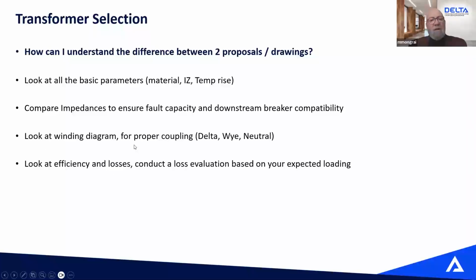Make sure the winding diagram has the proper coupling. Is it delta, is it Y, do I need a neutral? Again, look at your efficiency and losses, and you can conduct a loss evaluation. If you're buying a big lot of transformers or a large transformer, just don't look at your acquisition cost. Look, my transformer cost me 10 grand. That's the losses of the transformer. That's my cost of kilowatt.